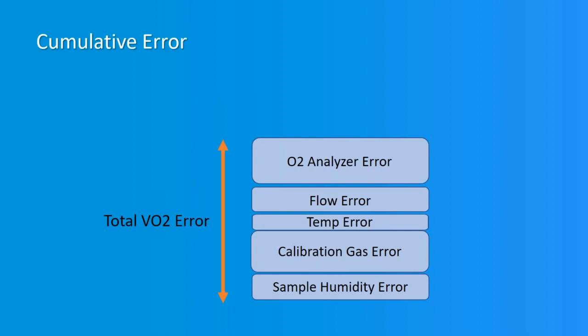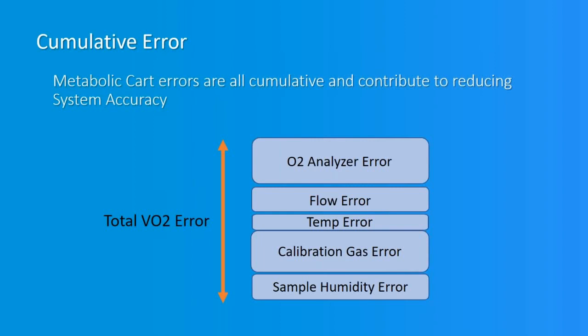To calculate cumulative error, first calculate the VO2 error contribution of each error source from the manufacturer's specifications over the likely testing range. Then the total VO2 error can be computed using the square root of the sum of the squares method for every contributor to VO2 error.